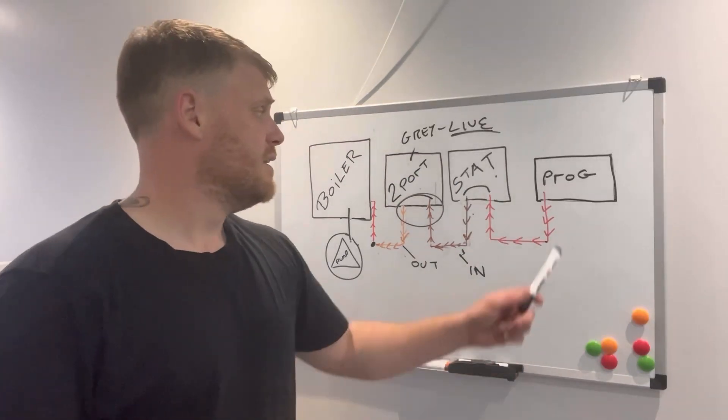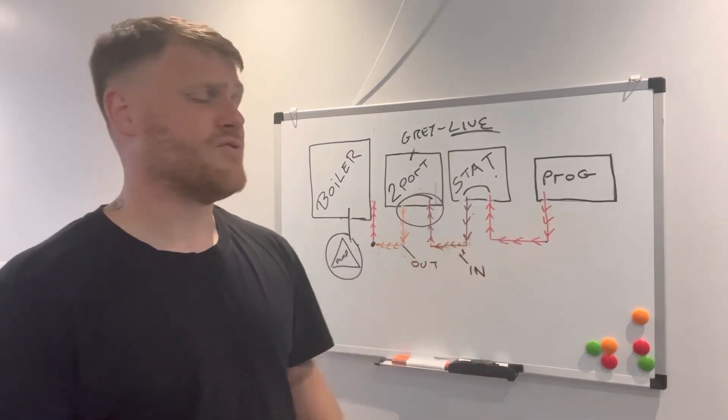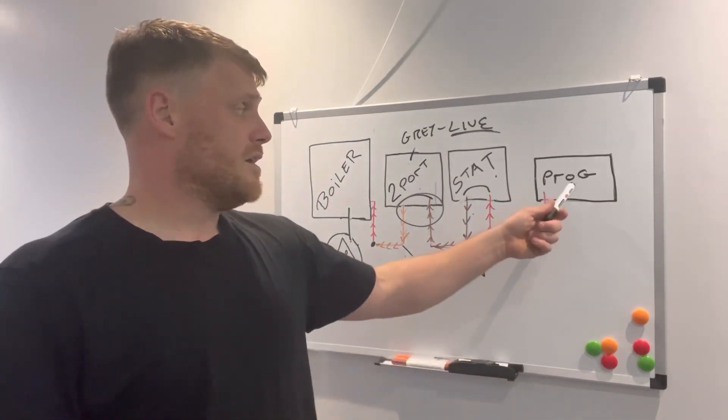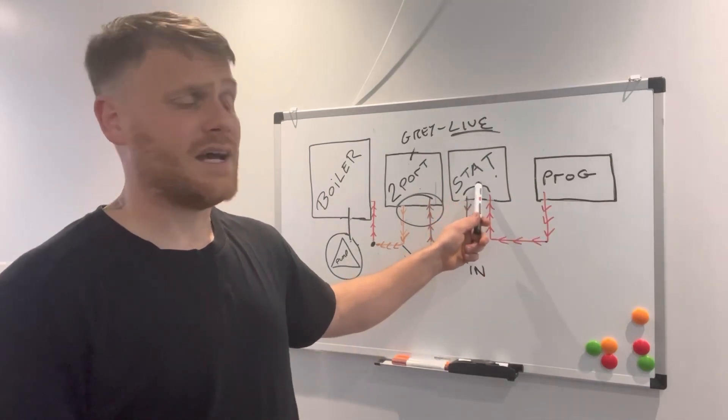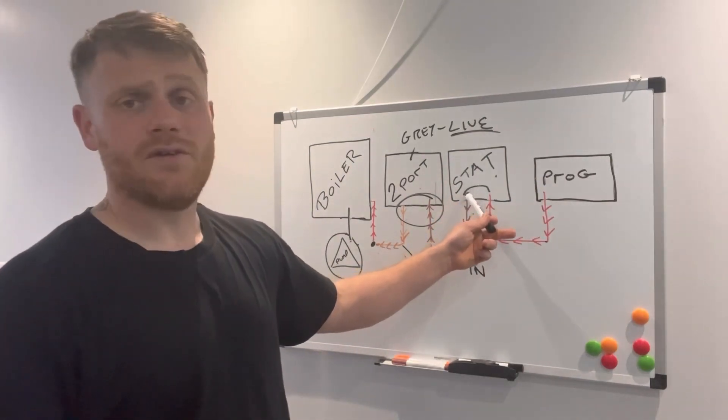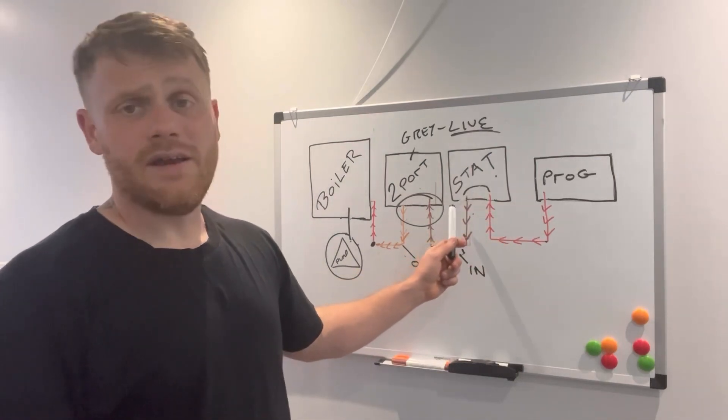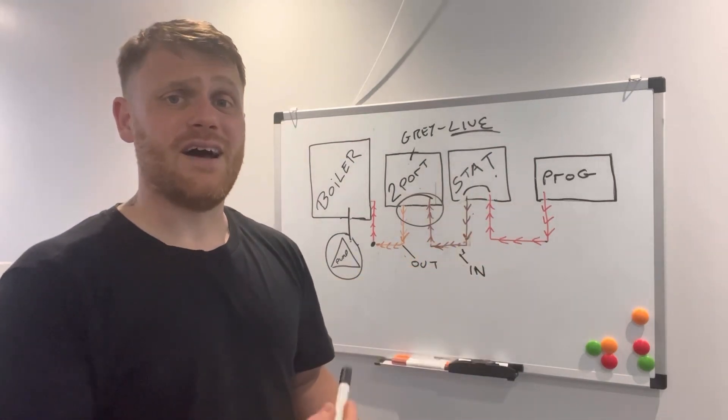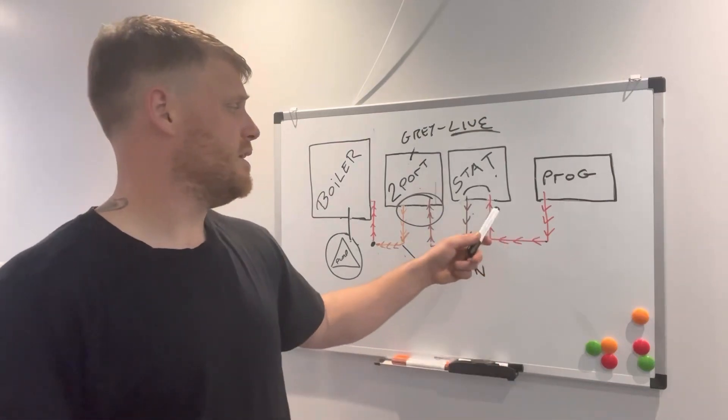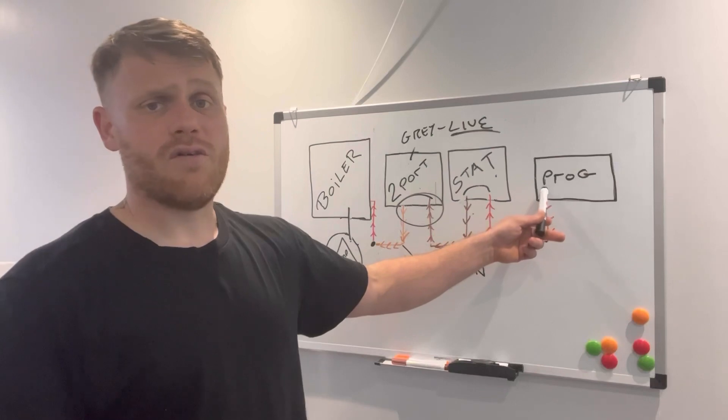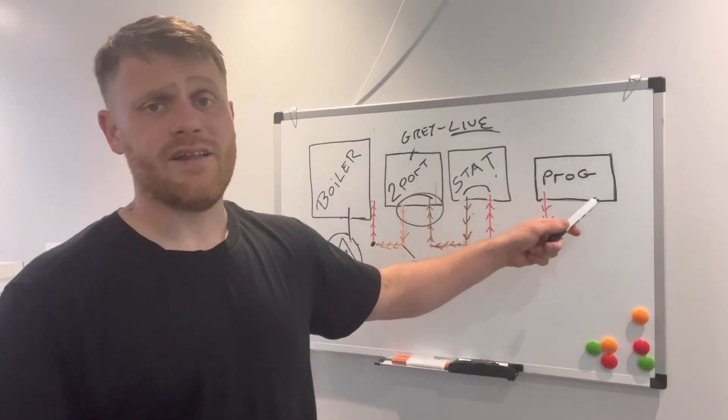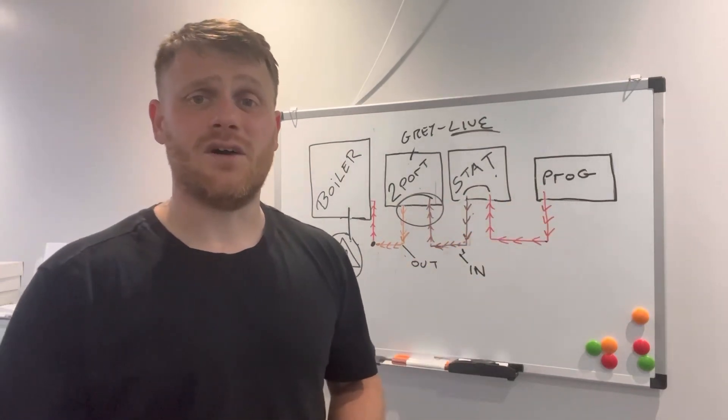And that's it, that is a simplified S-plan wiring. Just to cover the programmer and the stat, on the programmer you'll normally have, it's normally three and four on these, coming out whether it be heating or hot water. That'll be to the common on the stat, then that'll be coming out on the call on the stat. It depends on the make and model of the stat and the programmer where them wires goes, but normally it's common and call.